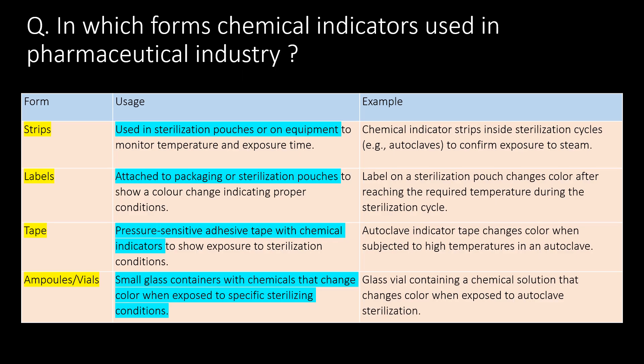In which forms are chemical indicators used in the pharmaceutical industry? You can refer to the bullet tables for different forms of chemical indicators, their usage, and examples. Strip form is commonly used in sterilization pouches or on equipment to monitor temperature and exposure time. Label form is commonly attached to packaging or sterilization pouches. Pressure sensitive adhesive tape with chemical indicators are used to show exposure to sterilization conditions, whereas ampoules or vials are small glass containers with chemicals that color-change when exposed to specific sterilizing conditions.